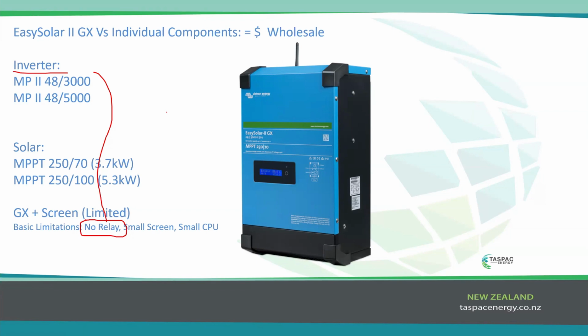So the inverters in the Easy Solar 2 GXs come in 3 kilowatts and 5 kilowatts, and the charge controllers respectively are 70 amps, which is equivalent to 3.7 kilowatts, and 100 amps, which is equivalent to 5.3 kilowatts of solar charging. Now you can put more solar onto them than that. You can put a substantial amount more if you want to. If they're off grid, that's all good. You can over PV it.